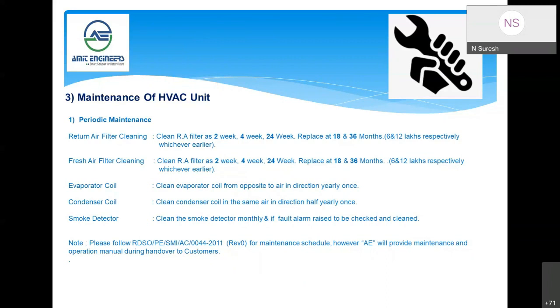For the smoke detector, clean it monthly, and if a fault is raised, it has to be checked and attended to immediately without any negligence. There are a few guidelines from RDSO, but those are for the filters and so on. For the smoke detector and others, based on the manufacturer's recommendation, we are also going to give guidance in the manual. I would request the end customers to strictly follow it, so that we can have a safe and reliable system.